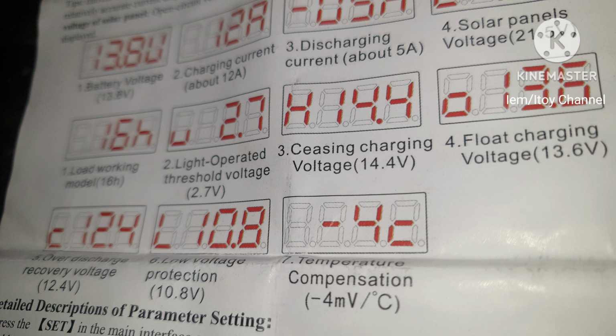Press and hold the button and we can set the parameters. First is the load working mode, and I think 16H is the on-off mode. Next is the load threshold voltage, followed by the high voltage disconnect. Next is the float voltage when reaching the high voltage disconnect, then the discharge battery recovery voltage. Next is low battery voltage cutoff, and the last is the temperature compensation setting.